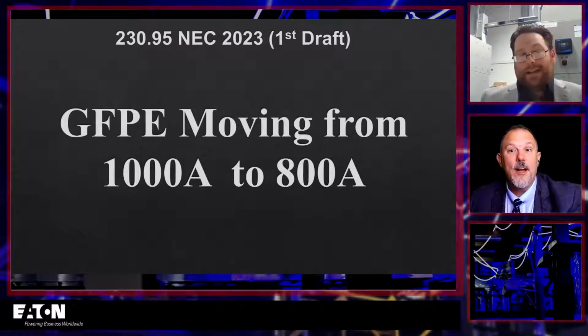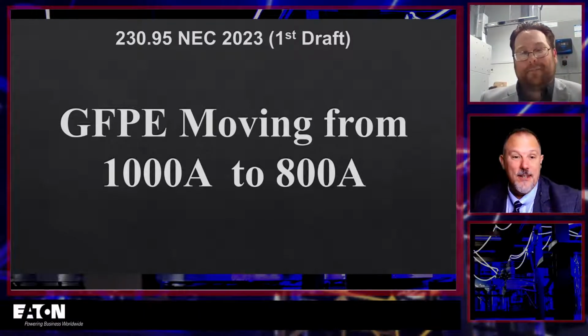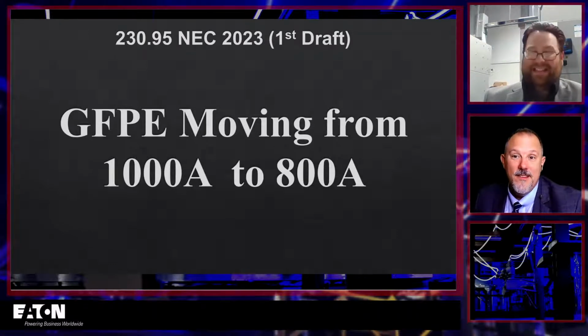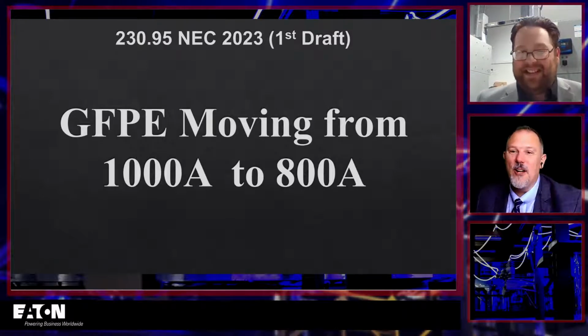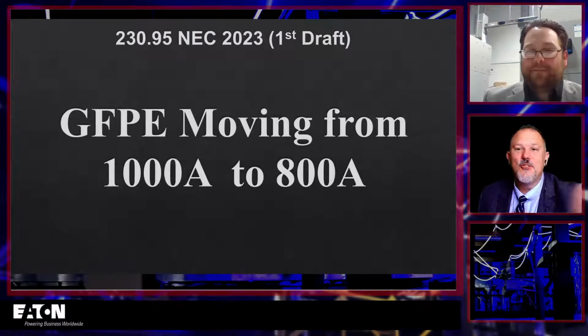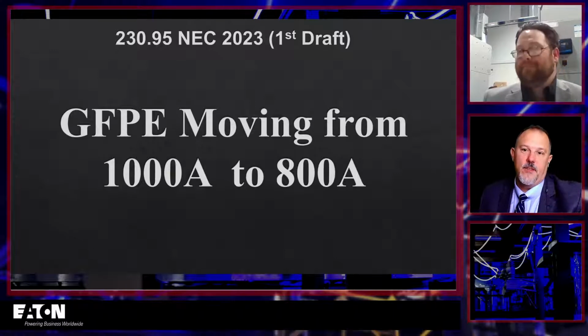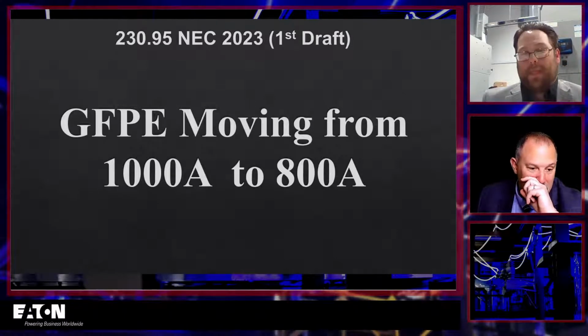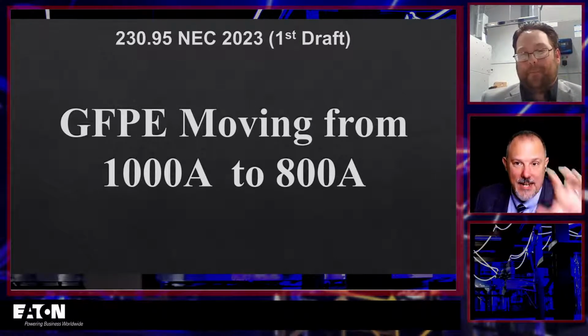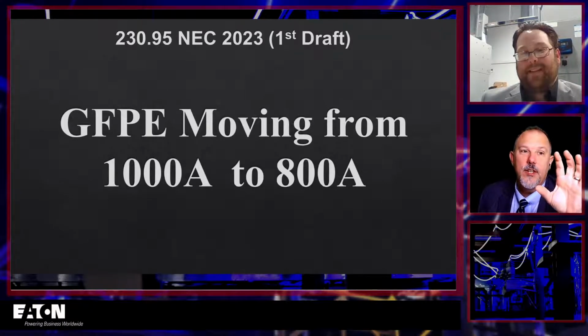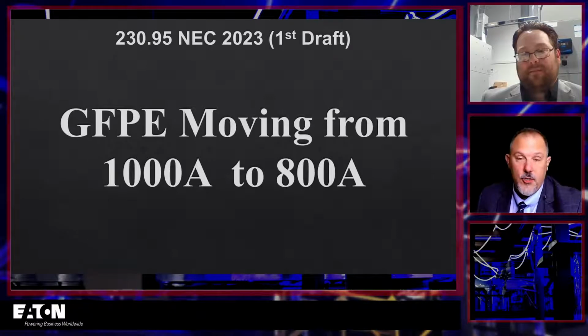And you know why? Here's what happens. And you know this, right? At 1,000 amps, if I want to avoid GFPE, what do I do? An 800 amp service all day long. All day long. Or I'll put in two smaller overcurrent protected devices. So here's the issue. The National Electrical Code is going to be eliminating, or has in the 2020 code, the ability to have a panelboard with 6 disconnects.